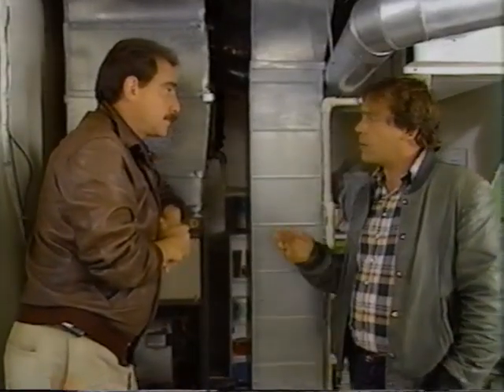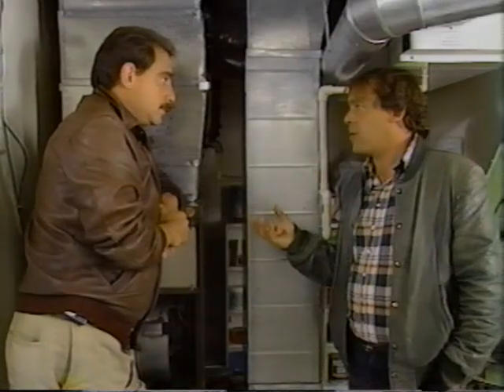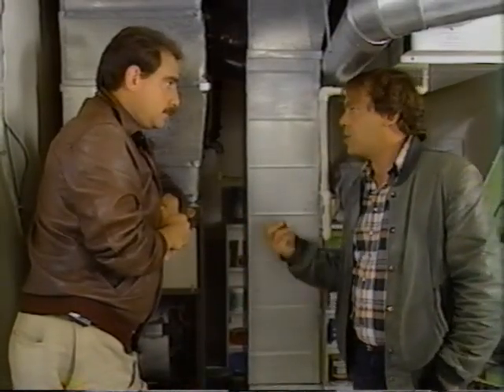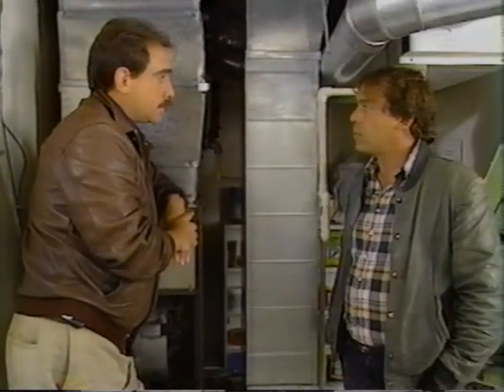Mm-hmm. Now, what about the fact with baseboards you can save money by turning off some of the rooms? There's sort of a zone control feature. You also achieve some zone control in this case, or really balance in this case, because when the original mechanical equipment is installed, dampers are put in all the ducts going to the various rooms in the house. Those are then adjusted to give the entire system balance. And the homeowner has additional control by working with the registers that are in every individual room.